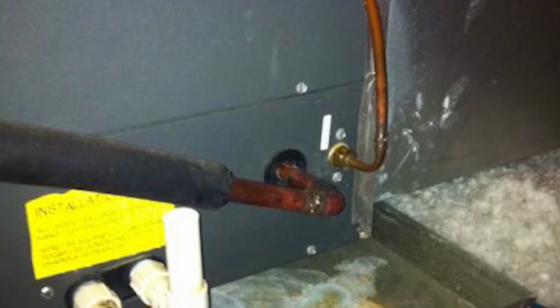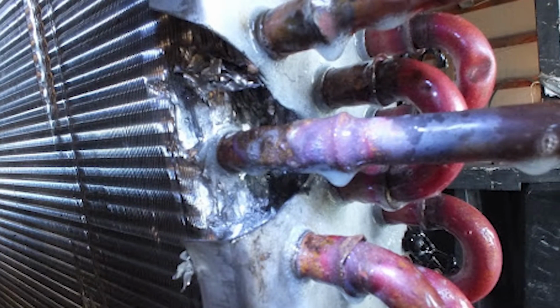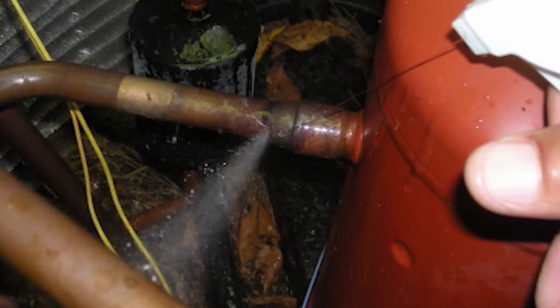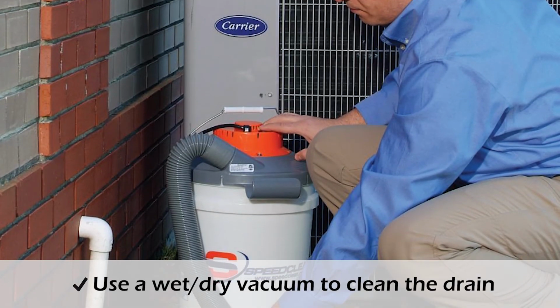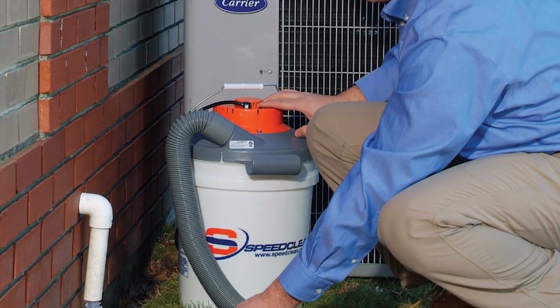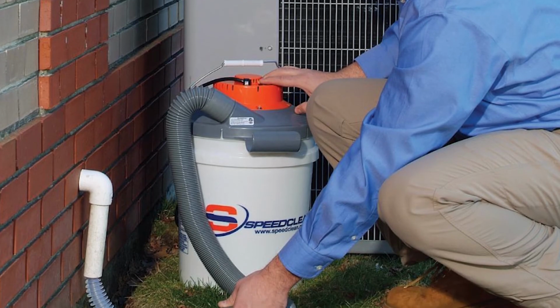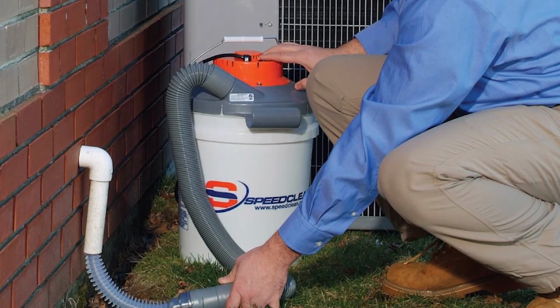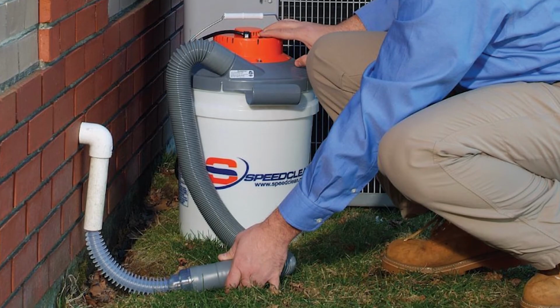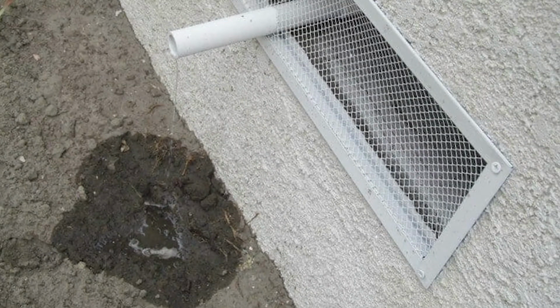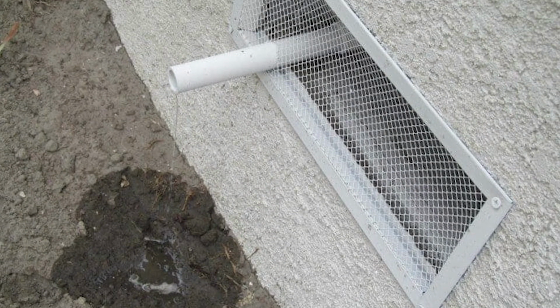If the refrigerant or coolant leaks or has holes in the system and the condensate drain line gets clogged, the water overflows and a drain float switch will shut down your AC to prevent any water damage. Use a wet-dry vacuum to clean the drain. Locate the main condensate drain line and connect the wet-dry vacuum's hose to the condensate drain line, then turn it on to suck out any obstructions. Wait around 3 minutes to ensure that the drain line is clean.